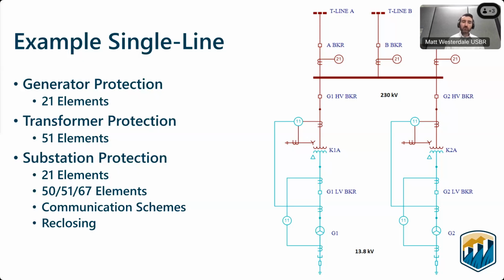For the PRC 27 applicable protective elements, we're going to have distance or 21 elements on our generators. Those elements look out into the system to provide backup protection, meaning they would only ever operate if there was some sort of uncleared fault or event on the system, so not primary protection, but backup protection.